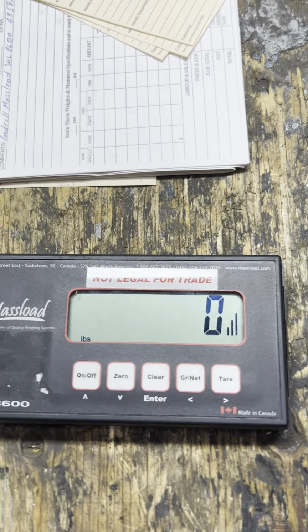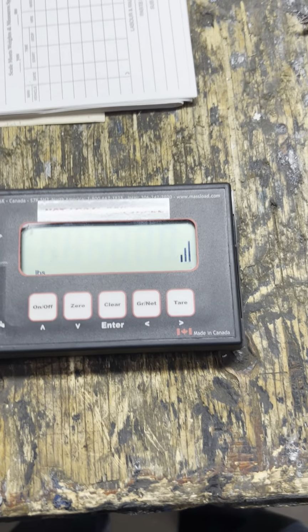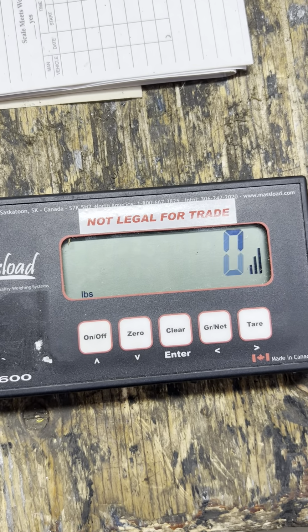you should move it to F1 and press the 0 button. This is our first point of calibration. We will have 5 of them. You can have 2, 1, as much as you can. I will use 5 because it's 50,000 pounds capacity and I will calibrate it each 10,000.